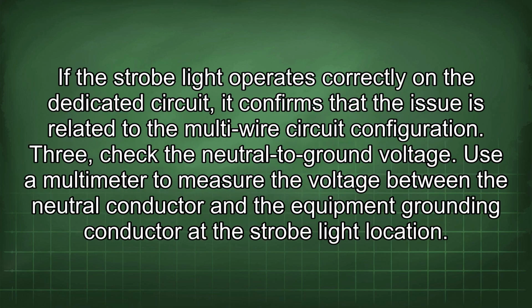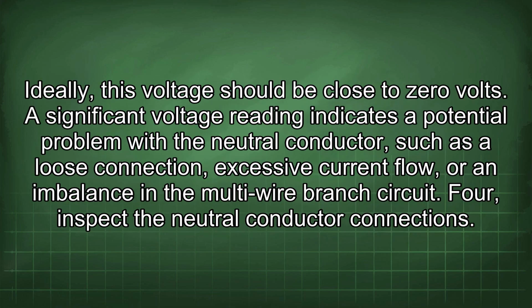If the strobe light operates correctly on the dedicated circuit, it confirms that the issue is related to the multi-wire circuit configuration. 3. Check the neutral to ground voltage. Use a multimeter to measure the voltage between the neutral conductor and the equipment grounding conductor at the strobe light location. Ideally, this voltage should be close to 0 volts. A significant voltage reading indicates a potential problem with the neutral conductor, such as a loose connection, excessive current flow, or an imbalance in the multi-wire branch circuit.